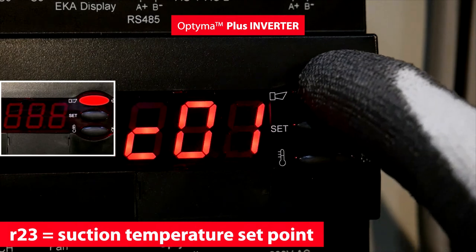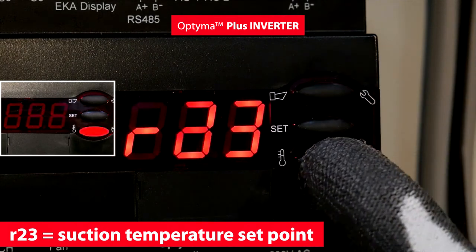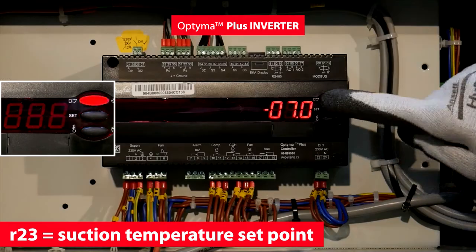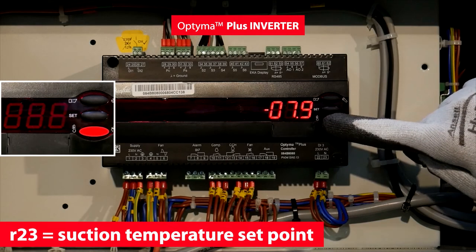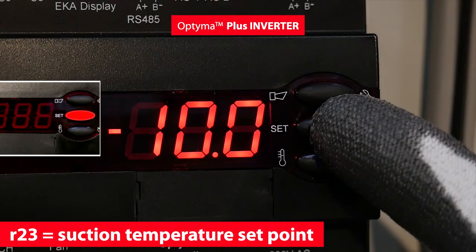For the Optyma Plus Inverter unit, set the suction temperature with the R23 parameter. The value is based on your evaporating temperature. In this example, minus 10 degrees Celsius.